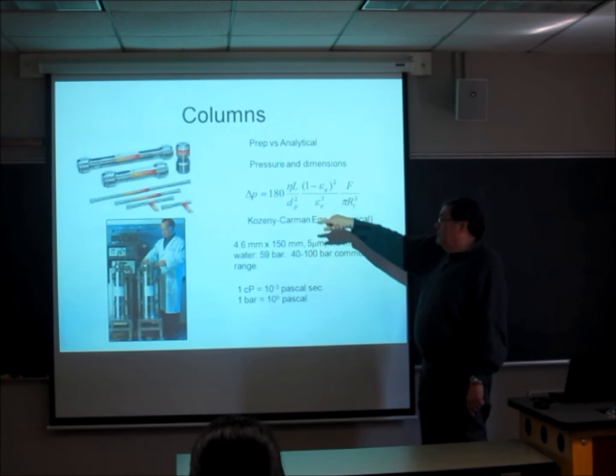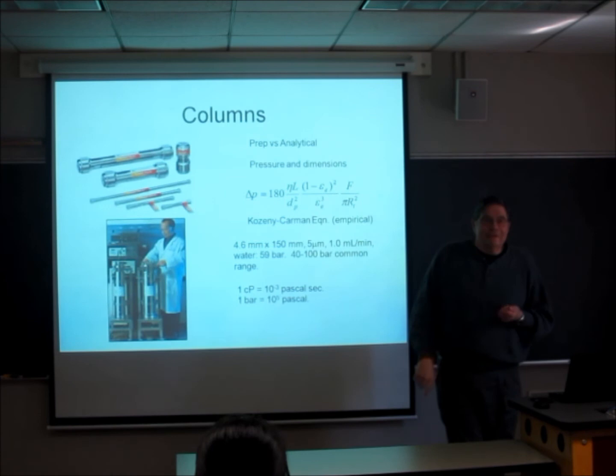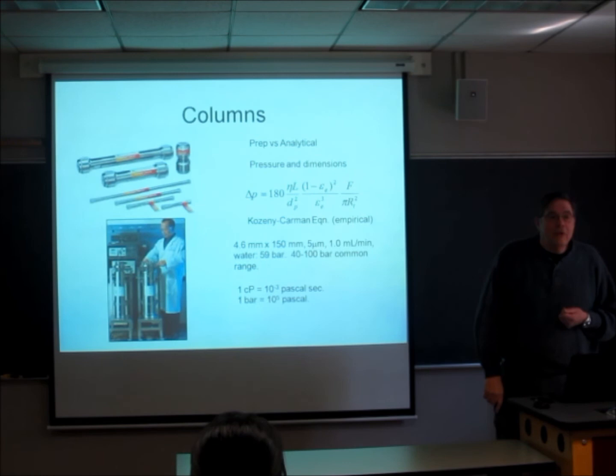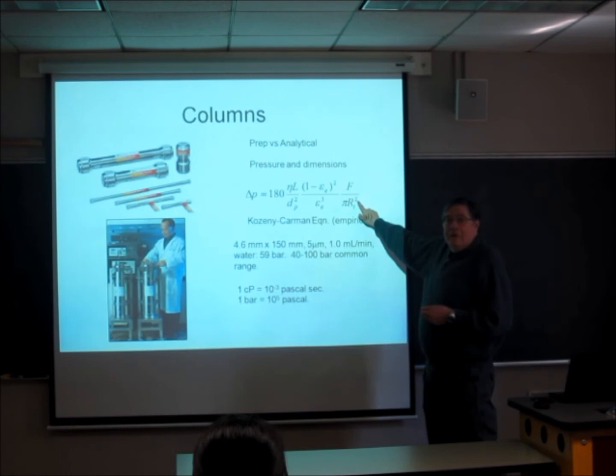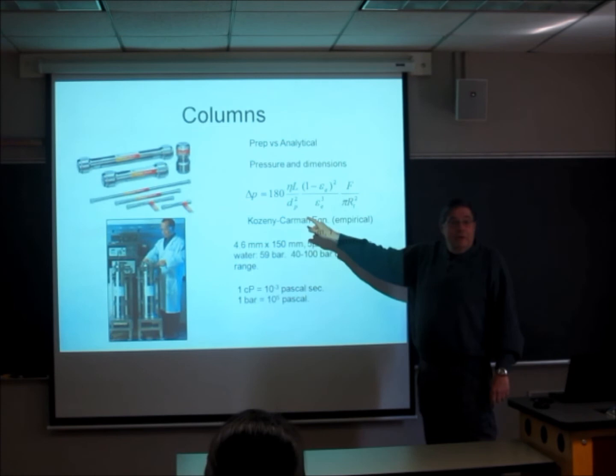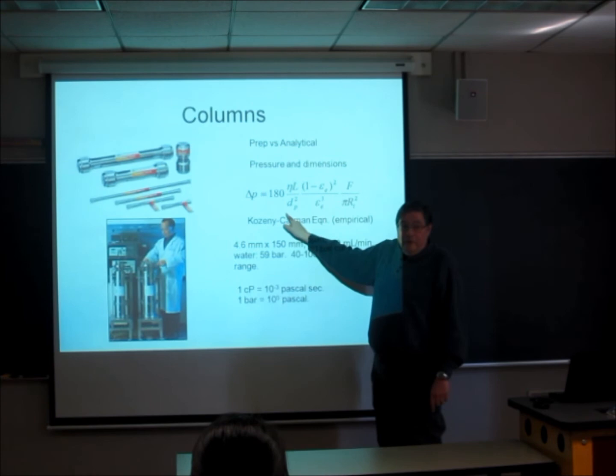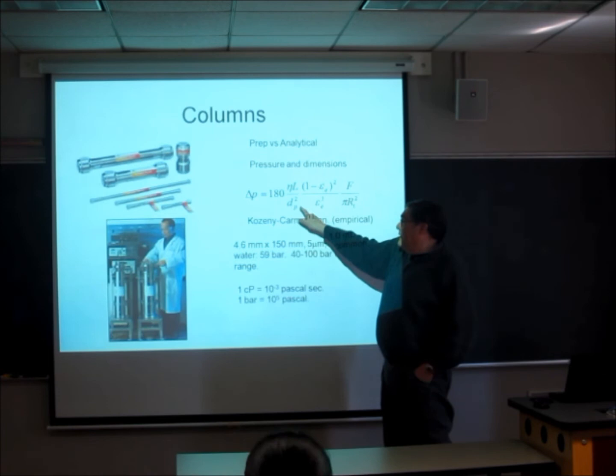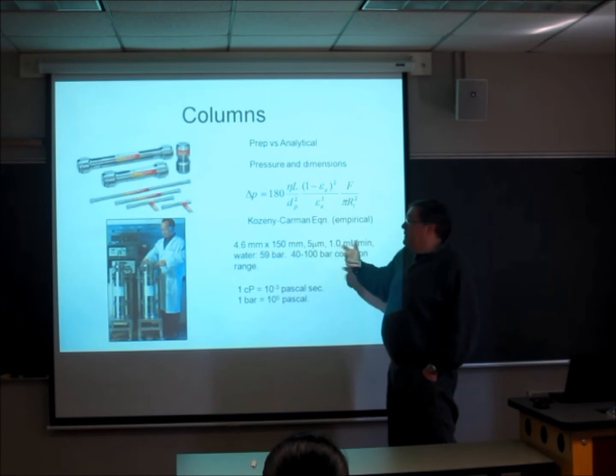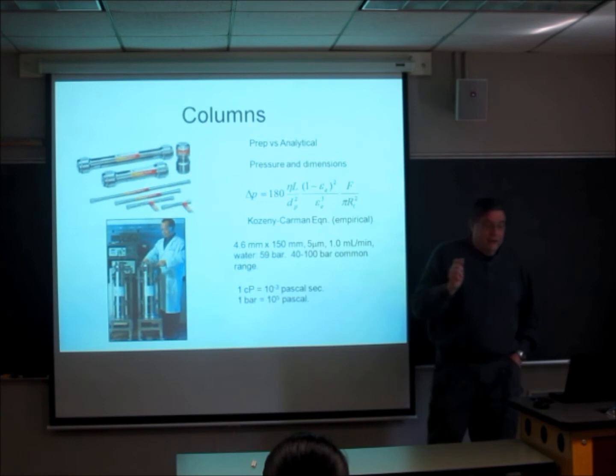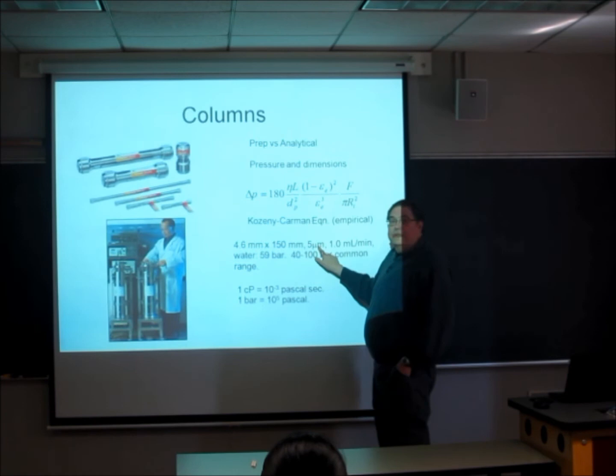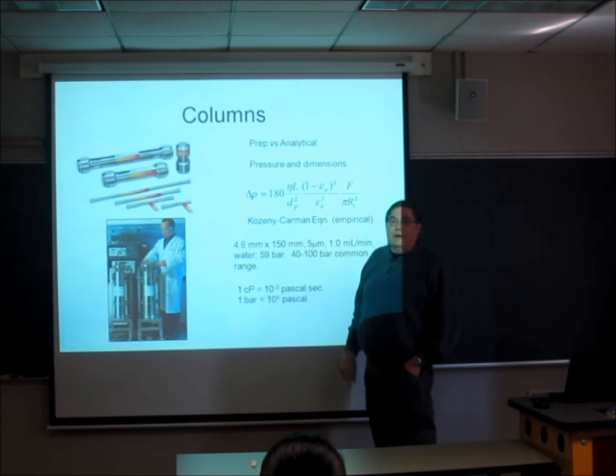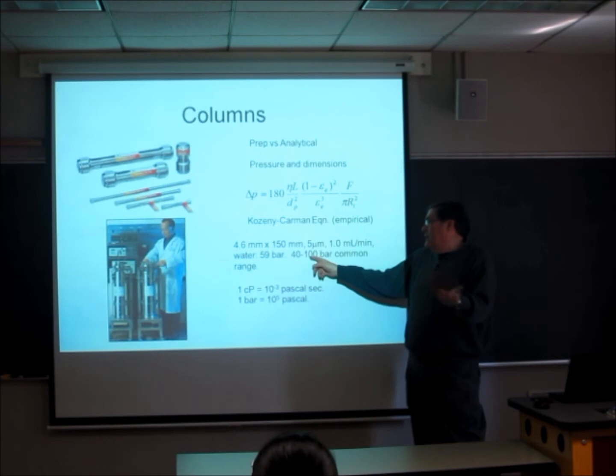Here's the flow rate. You double the flow rate, this is one mil per minute. If you go to two mils per minute, you'll double the pressure drop. Going to two mils a minute, you'd expect to double this for about 120 bars. This is the radius, the internal radius of the column. If we cut that radius in half, that's a quadruple, four times the pressure, because this is the radius squared. This is a very important one, the size of the particle diameter.